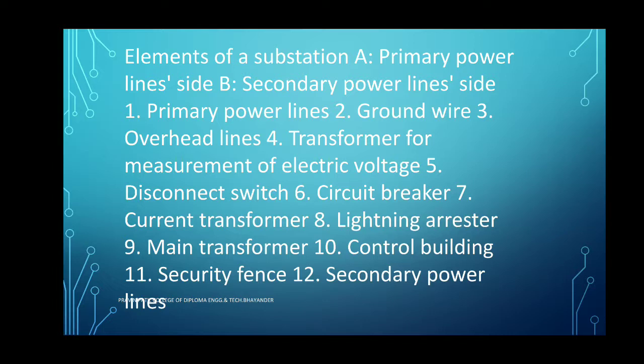Disconnecting switch is also used for protection purposes. Different types of circuit breaker are used for disconnecting the continuity of supply and for the protection of the electrical substation. Current transformer is used as the current measurement device. Lightning arrestor is used for protection from over voltage. The over voltage is diverted to the earth with the help of the lightning arrestor. One terminal of the lightning arrestor is connected to the overhead line and the other terminal is connected to the earth.